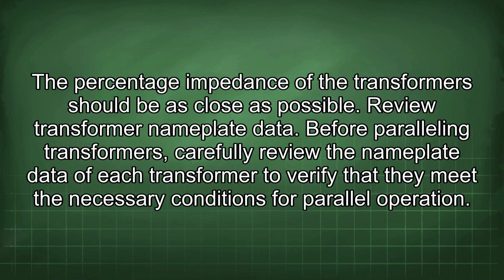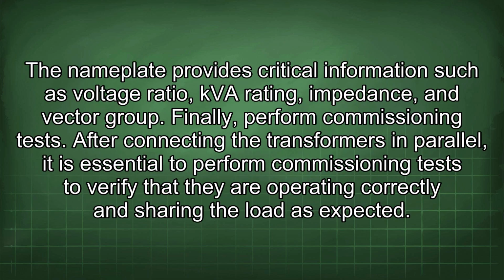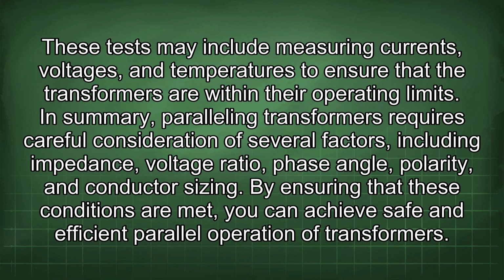Review transformer nameplate data. Before paralleling transformers, carefully review the nameplate data of each transformer to verify that they meet the necessary conditions for parallel operation. The nameplate provides critical information such as voltage ratio, kVA rating, impedance, and vector group. Finally, perform commissioning tests. After connecting the transformers in parallel, it is essential to perform commissioning tests to verify that they are operating correctly and sharing the load as expected. These tests may include measuring currents, voltages, and temperatures to ensure that the transformers are within their operating limits.